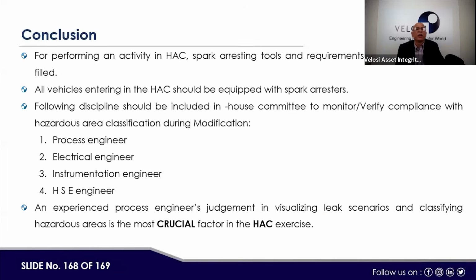Then, what is the conclusion? Once the HAC drawings are prepared, for any activity performed in HAC, spark arresting tools must be used and the PTW requirement should be fully filled. A vehicle entering the HAC should be equipped with spark arresters. The following disciplines should be included in an in-house committee to monitor and verify compliance with the hazardous area classification during modification: process engineers, electrical engineers, instrumentation engineers, and HSE engineers. The experienced process engineer's judgment in visualizing leak scenarios and classifying hazardous areas is the most crucial factor in the HAC exercise.